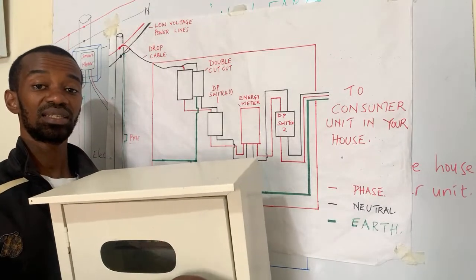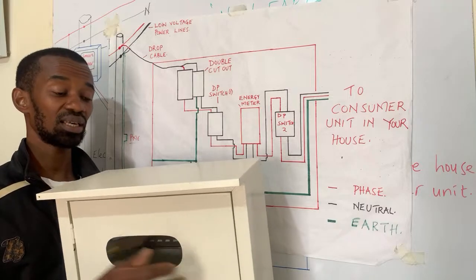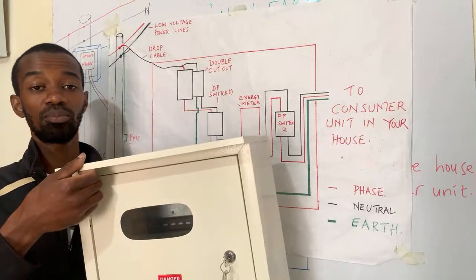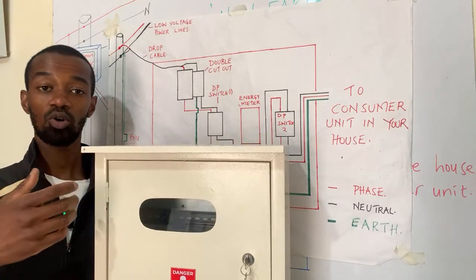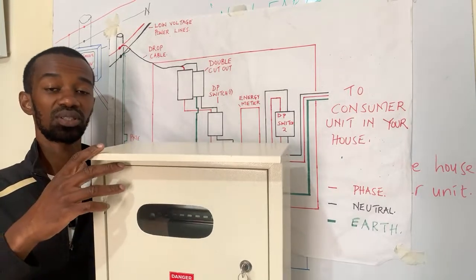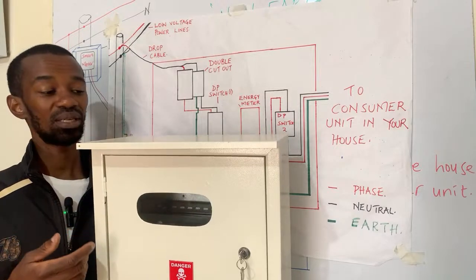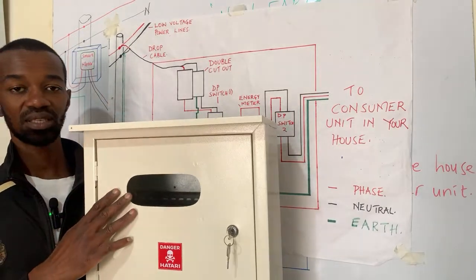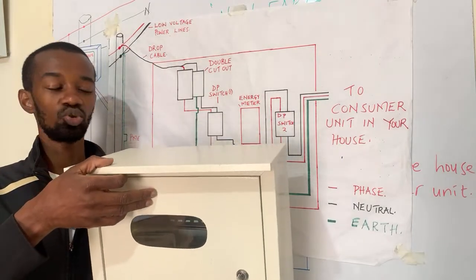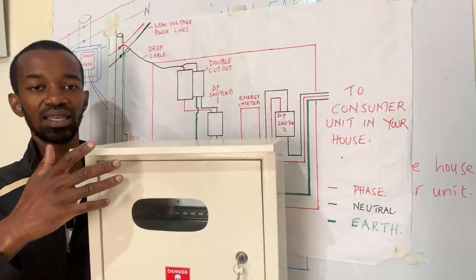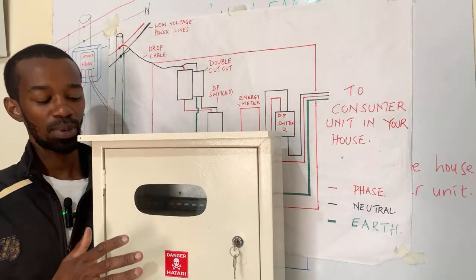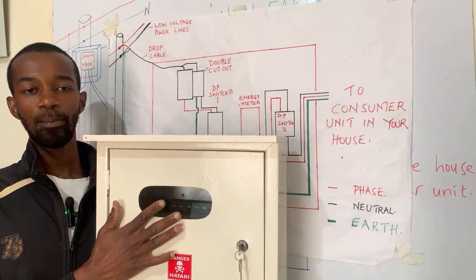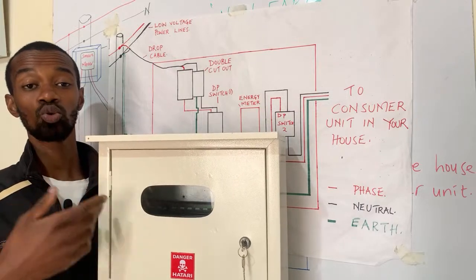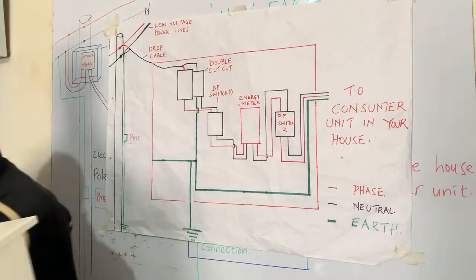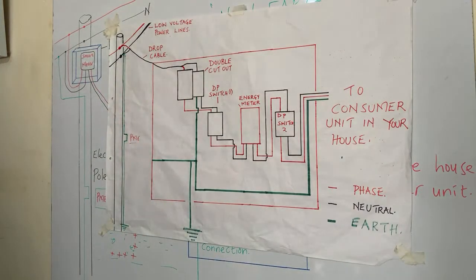If there is arcing that is happening in the meter box, which you can expect as long as it's an electrical installation, and some people may not be able to do regular maintenance work on their property, they will not really consider calling the electricians to do regular maintenance unless there is a problem. So once you have this type of meter box, then the connection is usually safe, because even if there is arcing, any fires or any sparking will only be happening locally in the meter box and will not escalate into burning that property. So that is a very important feature when it comes to the meter box and the safety aspect of it.